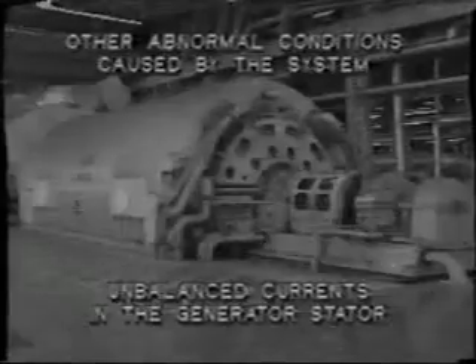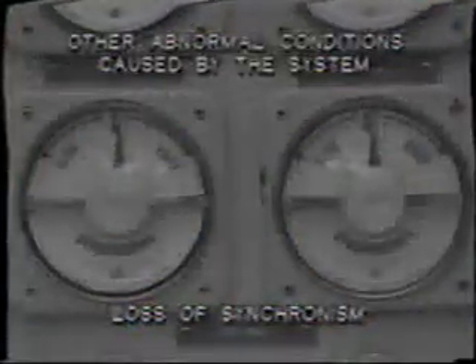Unbalanced currents in the generator stator due to serious system unbalance. This will cause overheating of the generator rotor due to negative sequence components. Loss of synchronism. If the unit falls out of step with the system, this could cause the rotor to slip a pole. Closing the generator breaker with the generator out of phase with the system. This could cause serious mechanical damage to the generator windings and the turbine. We will be looking at all of these items in more detail as we go through this tape and discuss the various protection schemes. But first, let's take a break and then we'll come back and look at protection schemes for phase-to-phase faults. For now, please switch off the tape and review this material in your workbook.